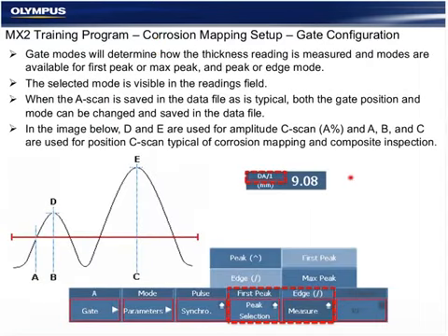The gate configuration, and shortly we're going to take a look at this live on the instrument through the webinar tool. We're just providing a little background. The newer versions of the OmniScan software contain 5 different options for gate configuration. If you're using an older version of the software with only 2, you will benefit enormously for this application by upgrading.